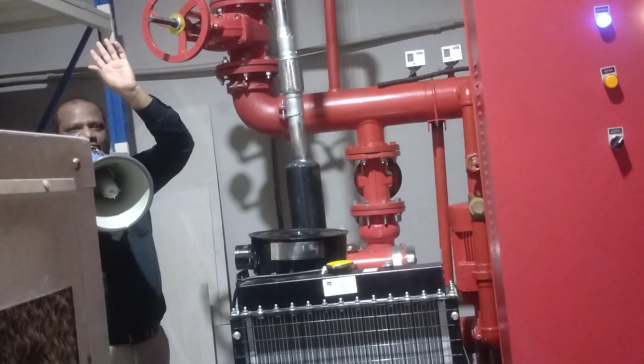In case a fire happens and a sprinkler bulb is lost, you have to replace the sprinkler bulb. At that time you have to close this valve; otherwise the water will keep coming from the network. For example, if there is a fire in the workshop area and the sprinkler bulb is lost, you have to close the valve, drain the water through the fireworks cabinet, and use scaffolding or a ladder to change the bulb. After that, you have to open the valve, and it will maintain the 6 bar line pressure.